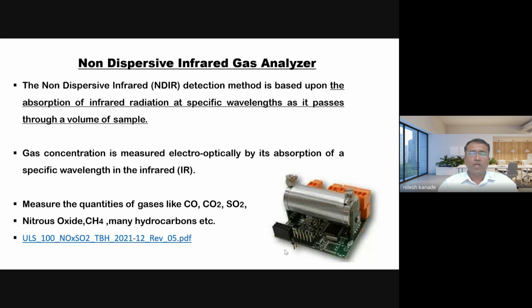This is the absorption of infrared radiation of a specific wavelength as it passes through the volume of the sample. When you pass a specific wavelength of infrared, the particular gas absorbs that infrared radiation, and the rate of absorption is directly proportional to the concentration of the gas. This is the simple measuring principle. It measures quantities of gases like carbon dioxide, carbon monoxide, sulfur dioxide, as well as nitrous oxides, methane, many hydrocarbons, etc.